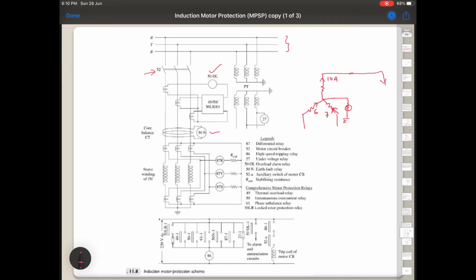You always know how current flows: outgoing current equals incoming current in a node. So it has to be actually 5 ampere in both these two phases, so that in balanced condition 5 plus 5 is 10 coming out here. But due to unbalanced current, I have taken 6 and 7 to show that it is not 5. So that difference current, which is 2 here and 1 here, 3 ampere will flow here. So when there is a difference of flow through the neutral, the relay will sense this difference current, and that is what makes it operate an earth fault relay.